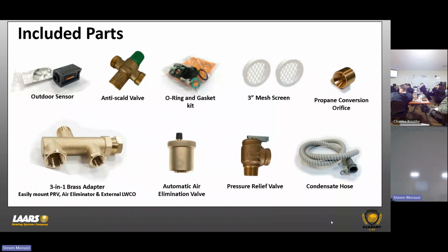I'm going to loosen this fitting, take this fitting off. Don't forget there's a gasket behind here, okay? So otherwise it's going to drop down. But again, we give you the gasket kit with an extra one. Orifice goes in. I'm going to retighten it. I'm done. What's left is my dip switch. I got to throw my dip switch to the propane position. I can convert this in probably 3 minutes. All right. Very easy product to convert. But don't forget your combustion analysis, guys.